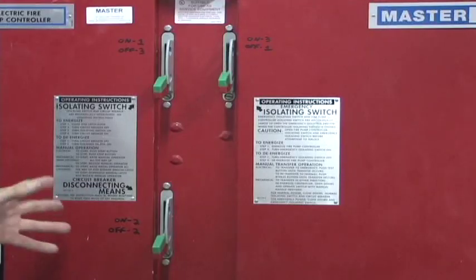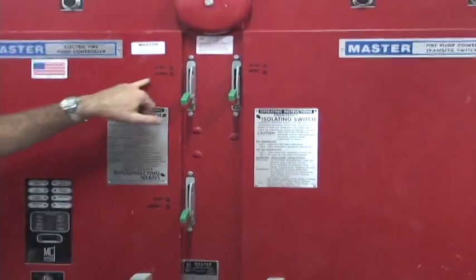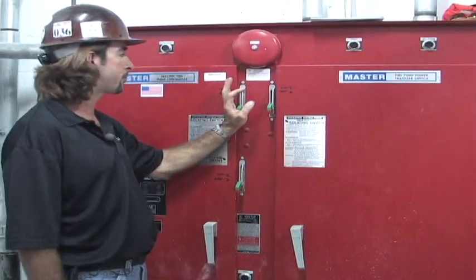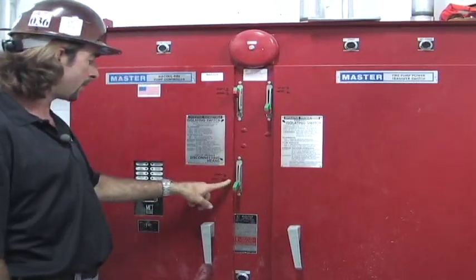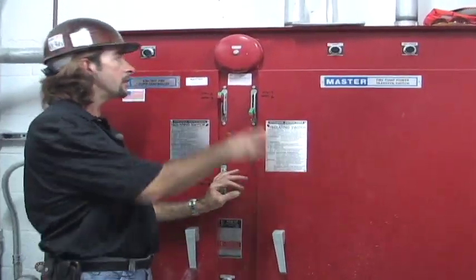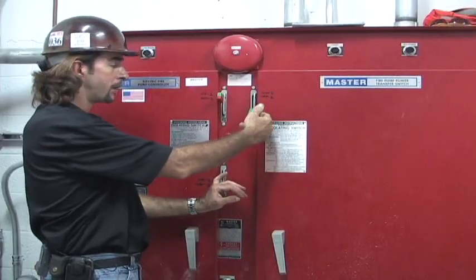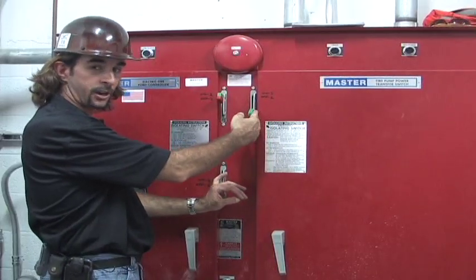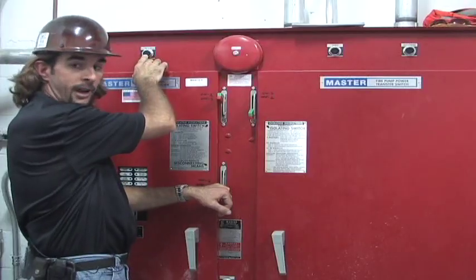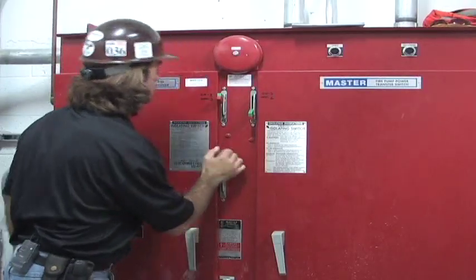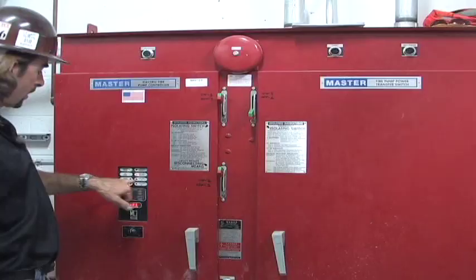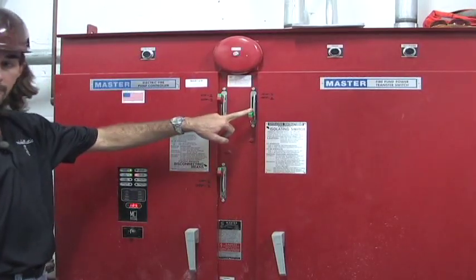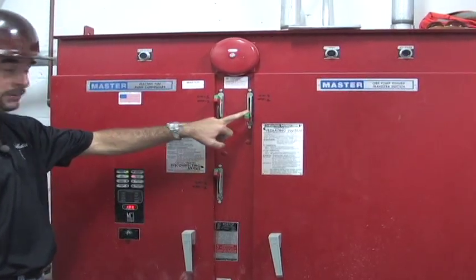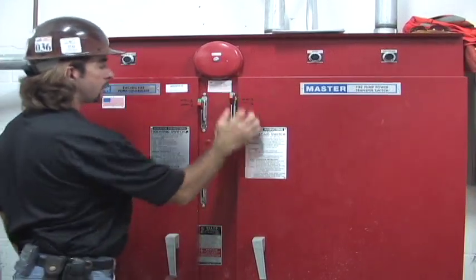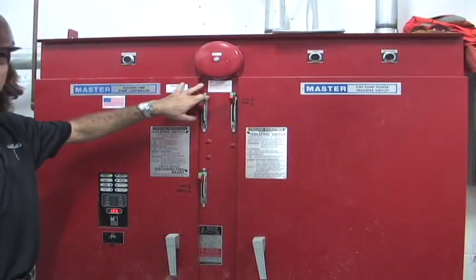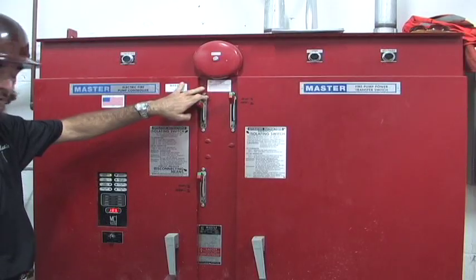Just opposite, counterclockwise, to turn it back on. To turn it back on, you're going to throw the number 1 switch. You're going to throw the number 2 switch, the disconnecting means. The alarm's going to go off saying that your emergency isolating switch is in the off position. We're going to hit the alarm silence button. Red light comes on saying that our isolating switch, emergency switch, is still in the open position. We're going to close that. Now the fire pump is ready for a manual or a low pressure start.